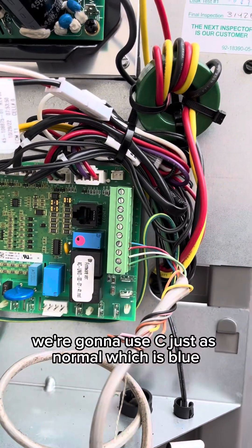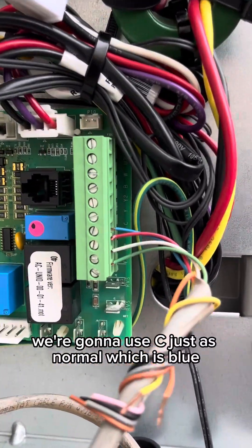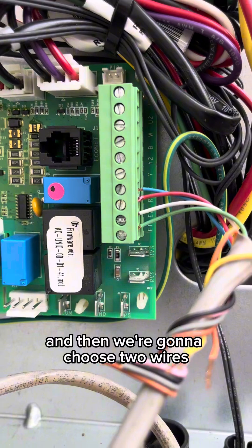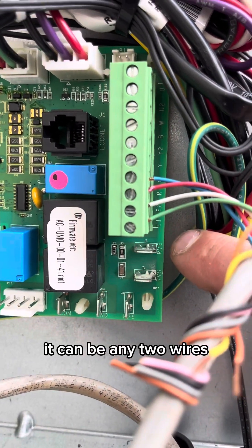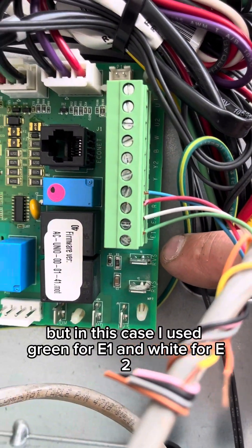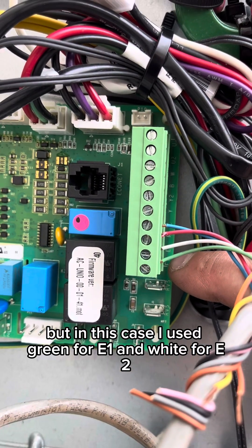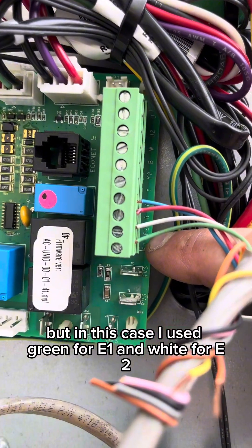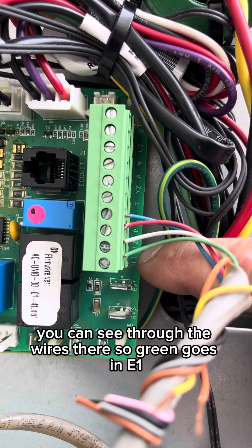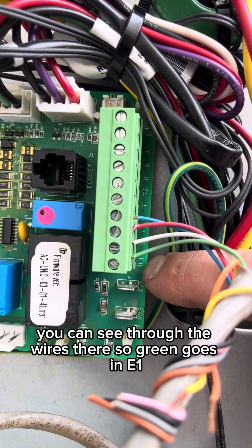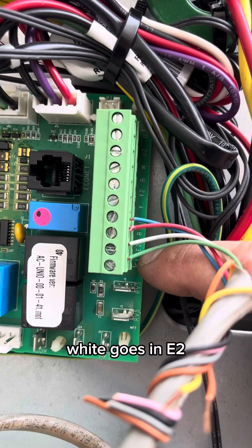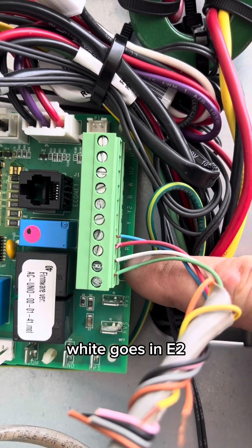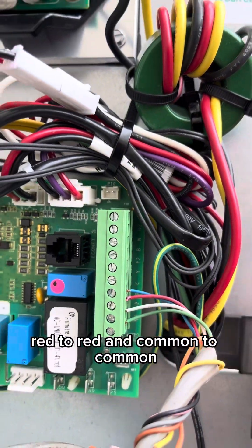We're going to use C just as normal, which is blue. And then we're going to choose two wires. It can be any two wires, but in this case I used green for E1 and white for E2. You can see through the wires there. So green goes in E1, white goes in E2, red to red and common to common.